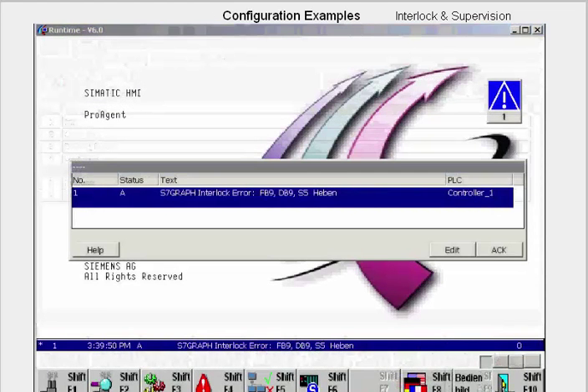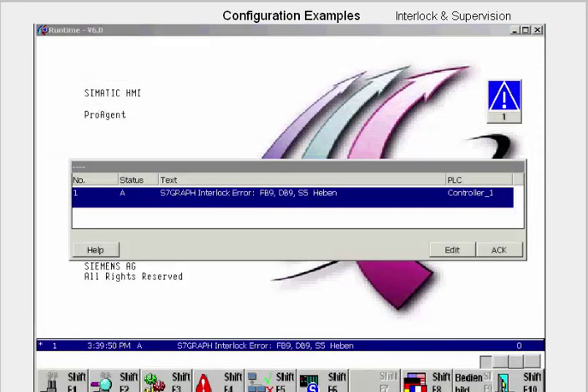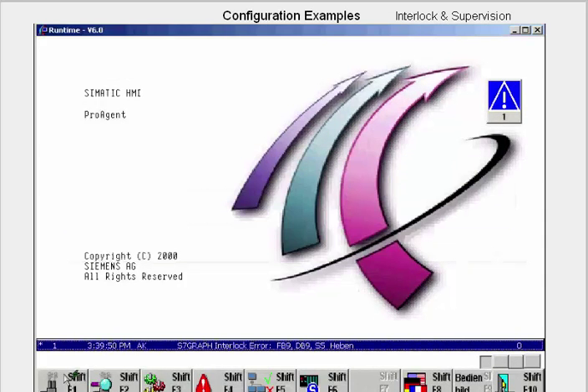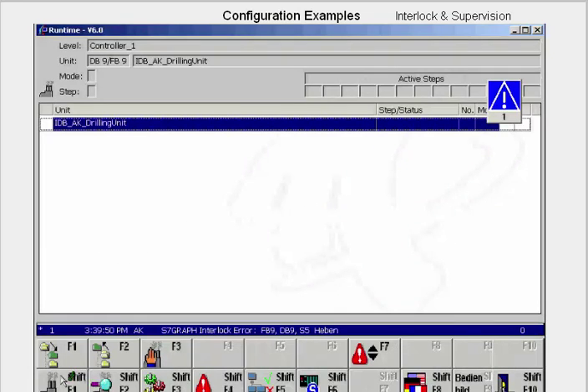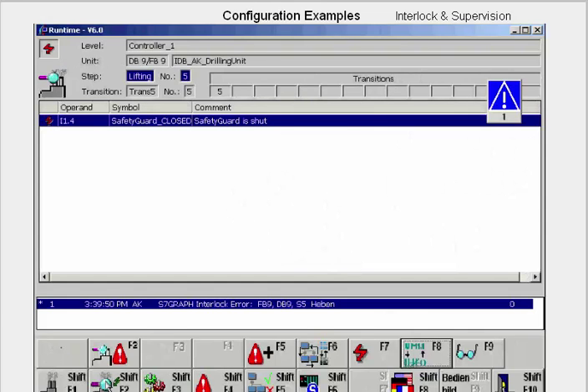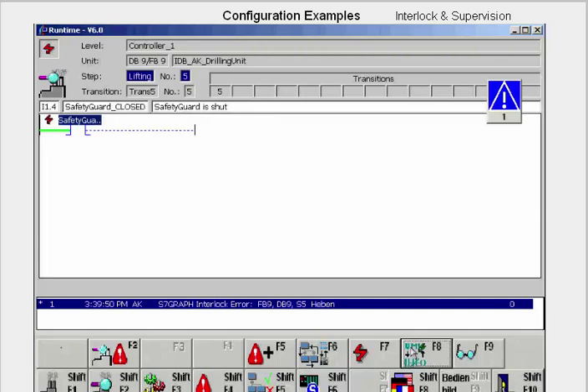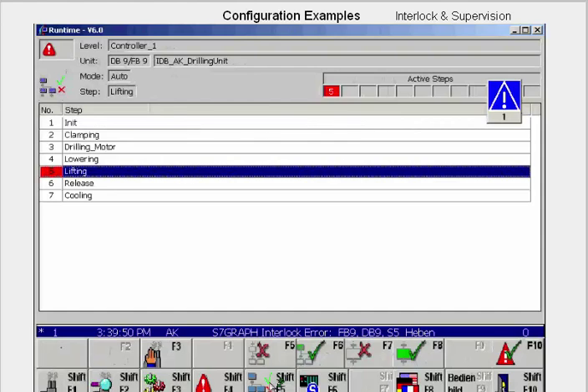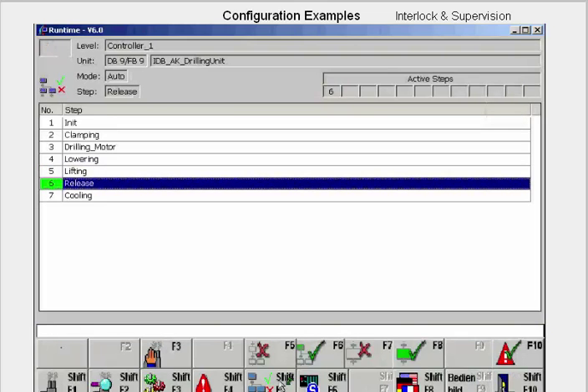If the safety guard is open during the lifting state, the interlock fault is announced. We acknowledge the fault and open the overview in which we can determine at which level and in which unit the fault has occurred. In the detailed picture, we see the step concerned and the transition as well as the address that caused the fault. With the F8 button, we switch to the statement list and ladder views to see how the address is linked in the program. In the sequencer view, just as with the supervision fault, the number of the faulty step is marked in red. Once the fault has been cleared, the sequencer starts to process again automatically, unlike with the supervision fault.